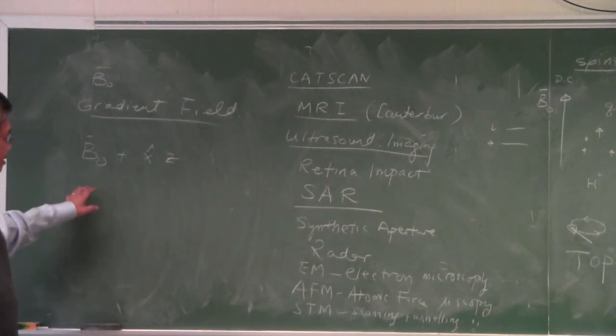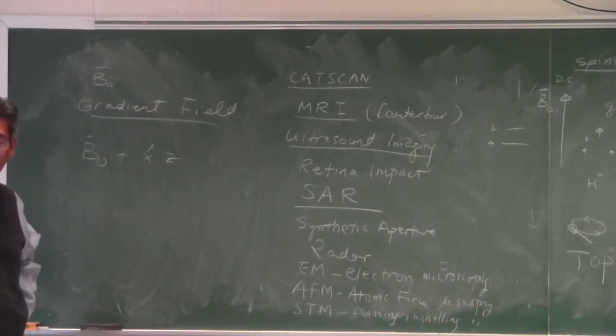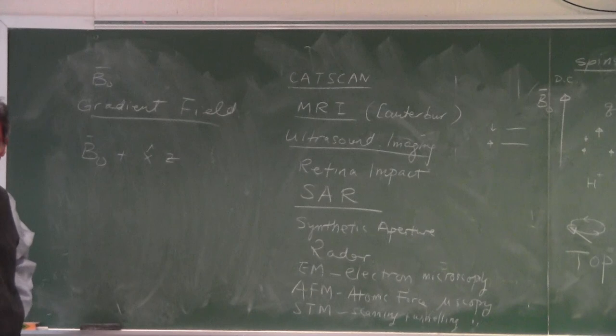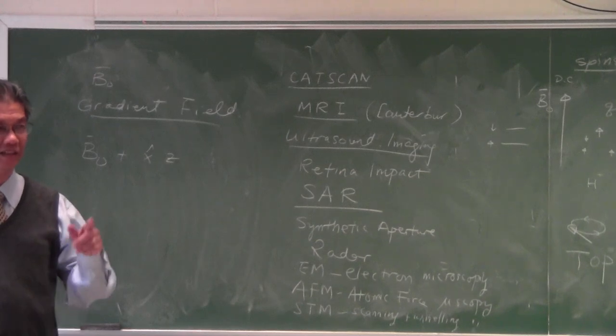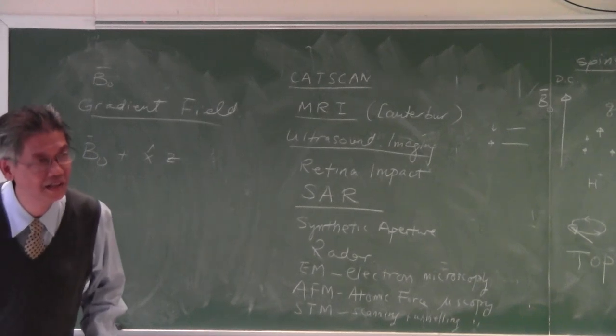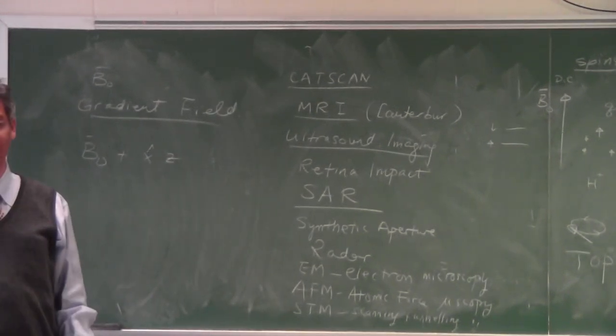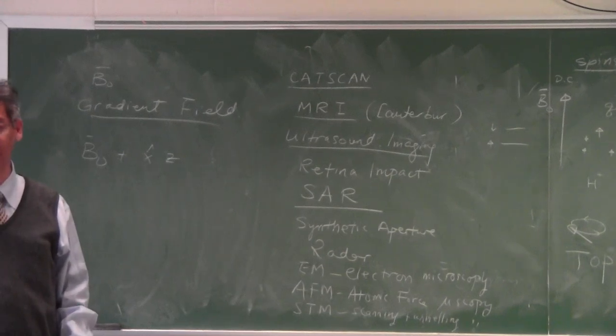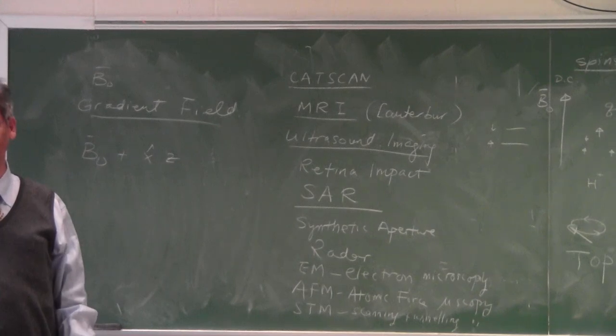So the best way is to actually heterodyne the system from 42 MHz down to the kilohertz range. Heterodyning means mixing — mixing the signal so that you can get some kilohertz signal out. And then you can do narrowband filtering. It's very hard to design a narrowband filter at 42 MHz, but quite easy to design one at the kilohertz range. So effectively you get a very narrowband filtering effect by heterodyning the electronics. The narrower the bandwidth, the sharper the MRI image would be. But what prevents you from designing narrower and narrower bandwidth electronics? Why can't you design electronics infinitely narrowband? Loss. Loss and quality factor — if you do super-heterodyning down to very low frequency, at 42 MHz if you want kilohertz bandwidth electronics, you have to have a Q of at least a thousand or more to design a filter.